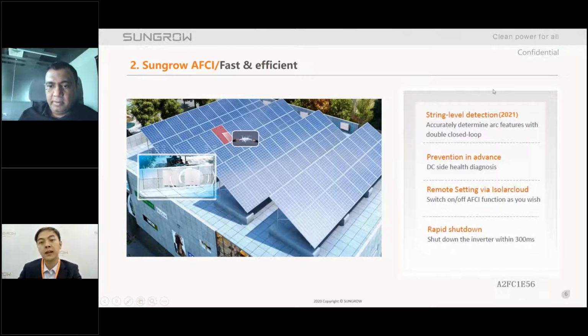In 2021, we will also update the AFCI function with string-level detection. Currently, if you have an arc, the inverter will cut it off, but you don't know exactly where the arc is, so it's hard to locate the arc fault. With this new function, in the near future you will have the ability to know exactly where the arc is, as the picture shows. You can quickly find the problem and solve it to bring your inverter back to work.